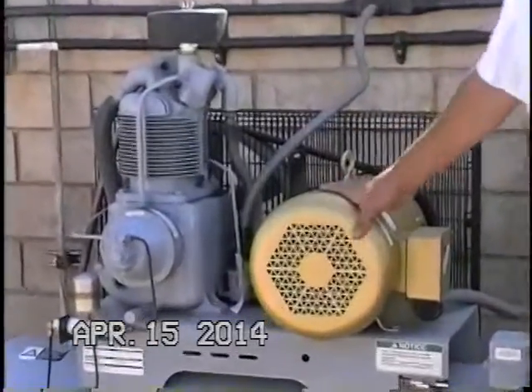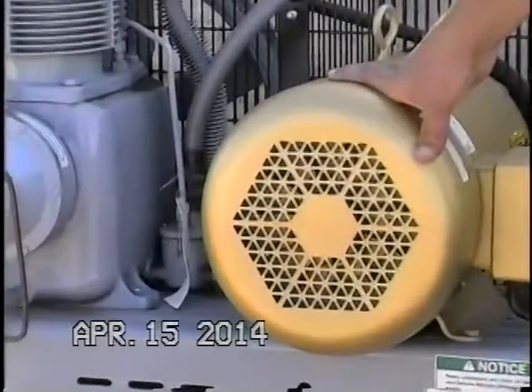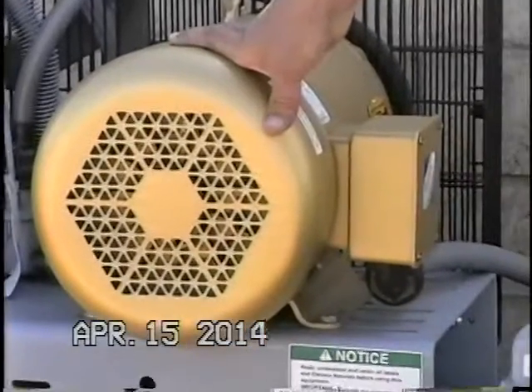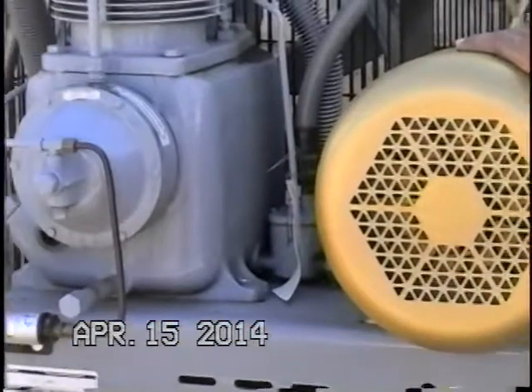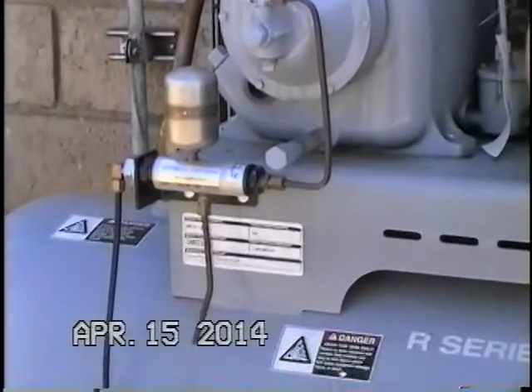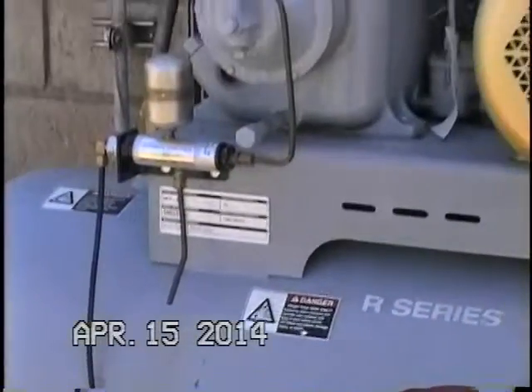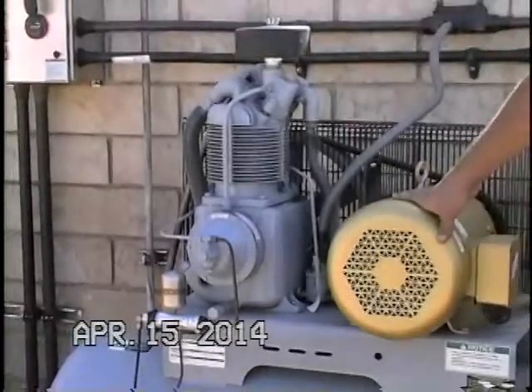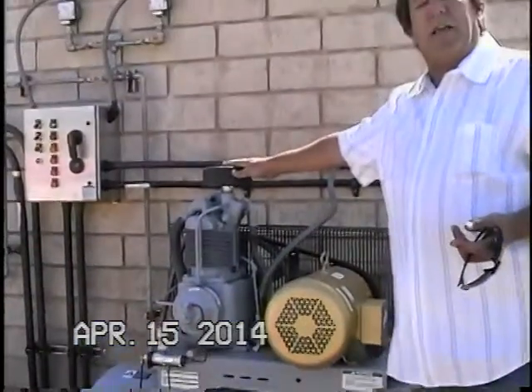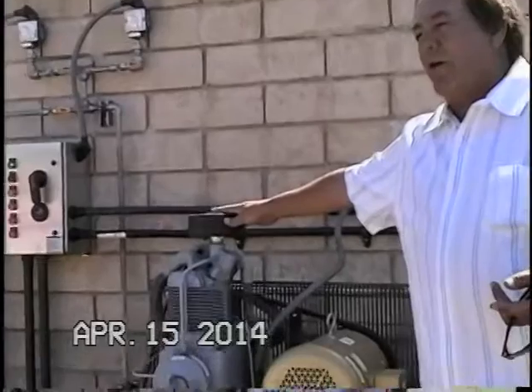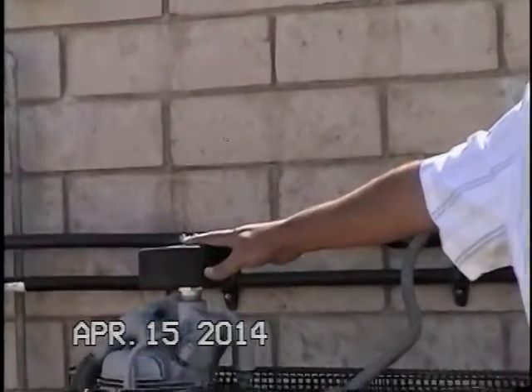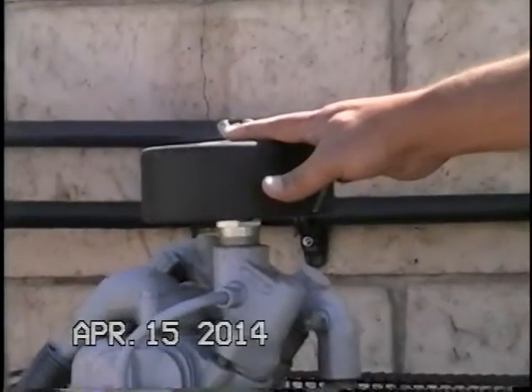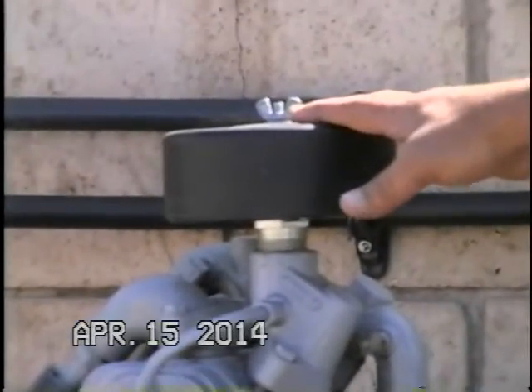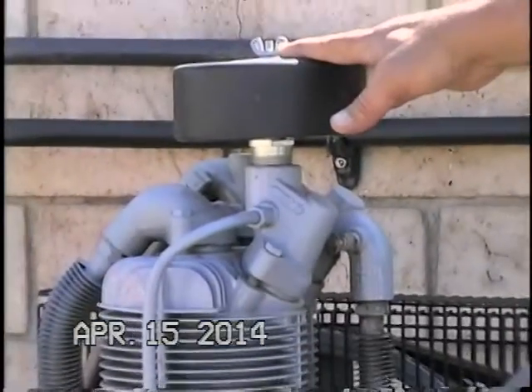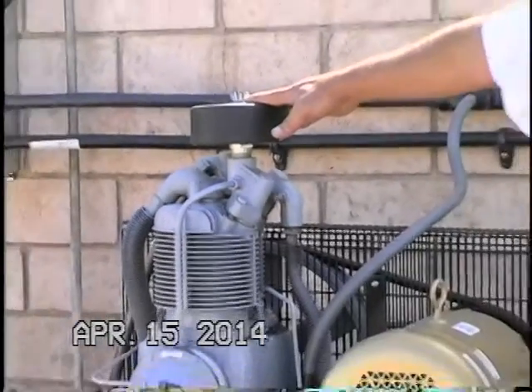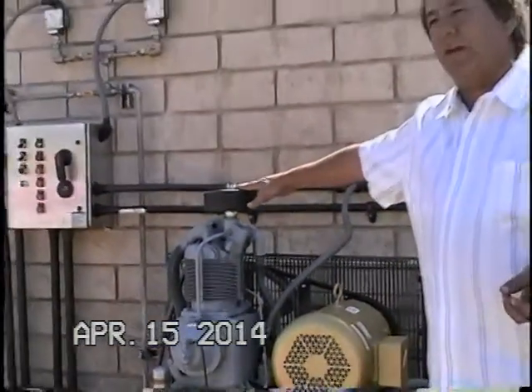The O&M manual for this compressor is inside your O&M manuals. You need to check the frequency of your oil changes, and there's not a lot of maintenance to these things other than oil changes and making sure you've got a clean filter. You know, a good visual on the filter. You don't really have a huge dusty condition out here. Your filter should last, I would say you need to replace it at least once a year. But other than that, a quick check of the filter would be great.